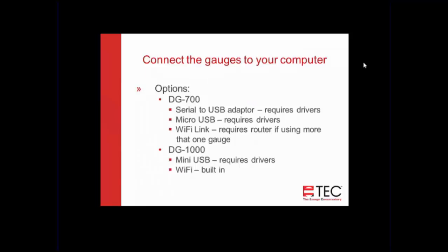So the procedure is you will have to make a connection. In order to use the software, you have to make a connection between the gauges and your computer. If you're using a DG700, you can use a serial to USB adapter, and that adapter will require drivers. Any of those cables you're using to connect the DG700 to a computer come with drivers and require that driver to be installed. The micro USB to USB cable, if you've got a gauge that's newer than 2009, then that micro USB cable came with it, and the drivers for that are on our website.